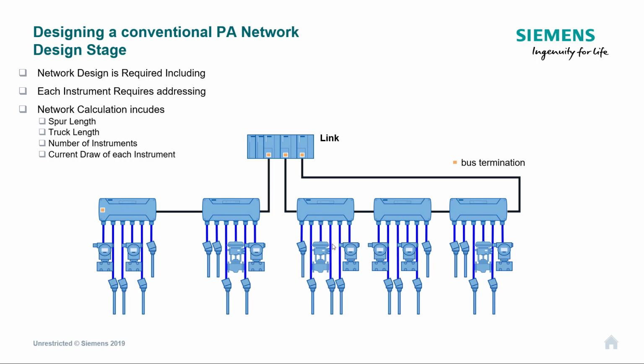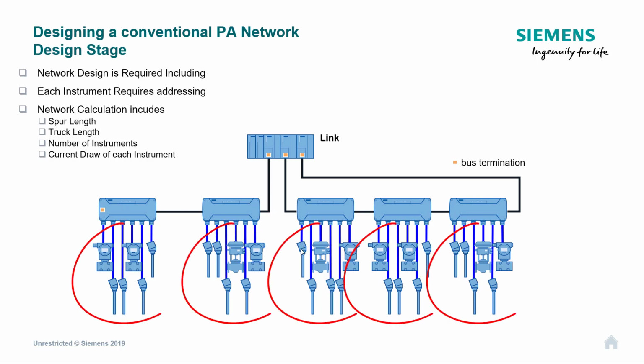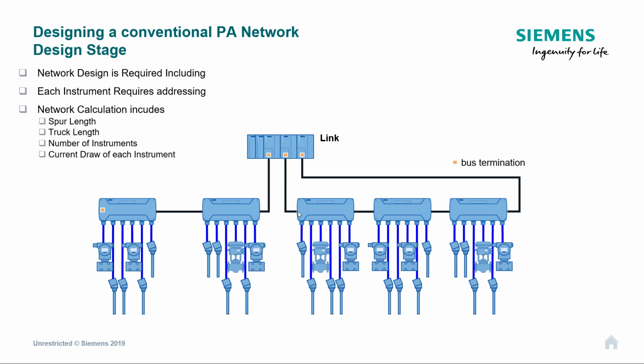So during the design stage, we have rules here for the connections to the instruments that we call spurs, the amount of instruments, the current they draw, and the length of the trunk, but also the amount of current that we can output via this coupler device. And then the header module here has a memory limit of 244 bytes. So we have to make sure that we design within those limitations.